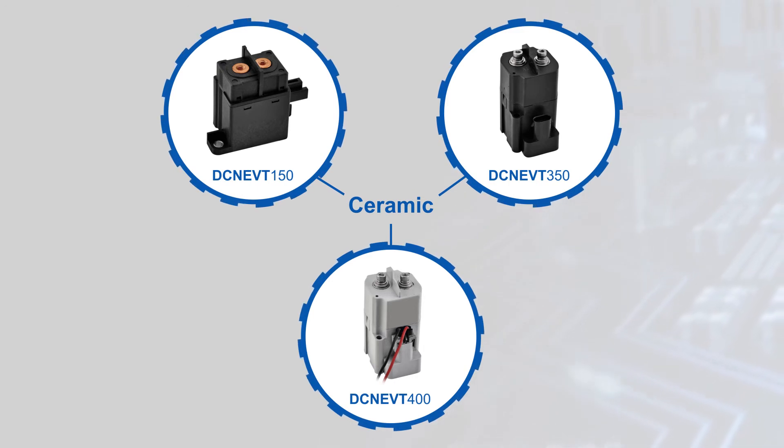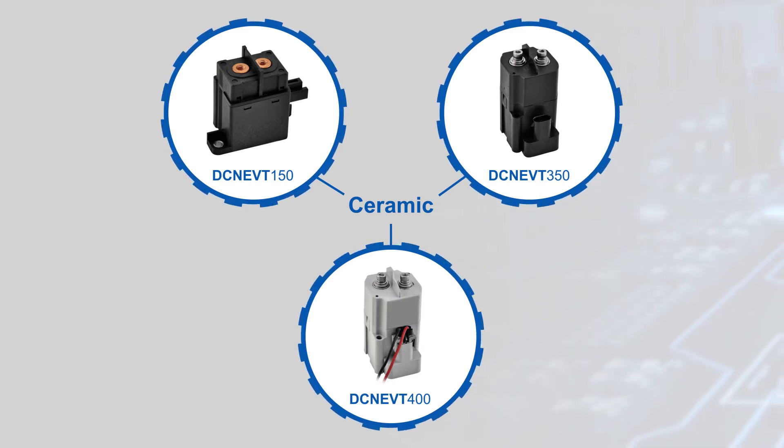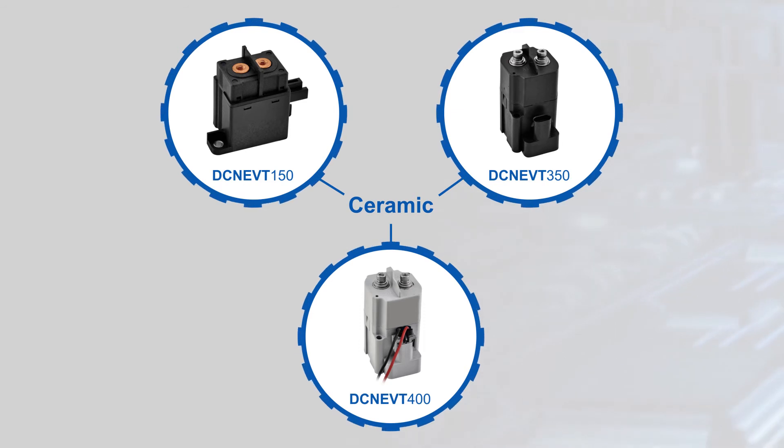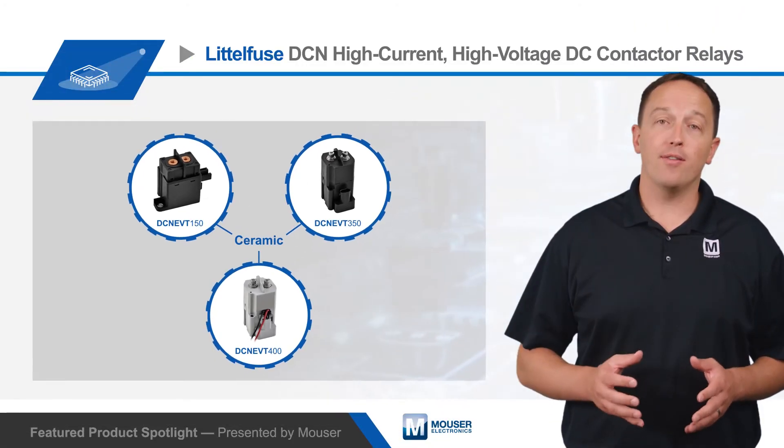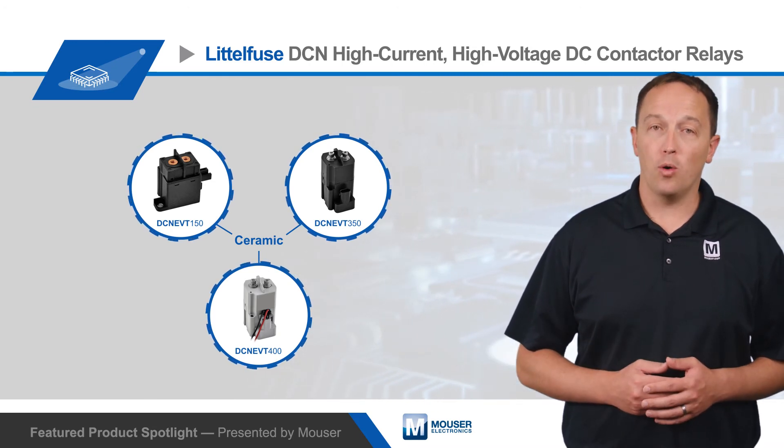Ceramic contactor relays have a sealed IP54 rated ceramic arc chamber that withstands higher pressures and temperatures for longer. They have ratings up to 1800 volts and 500 amps continuous carrying current with 12 volt or 24 volt DC coils.